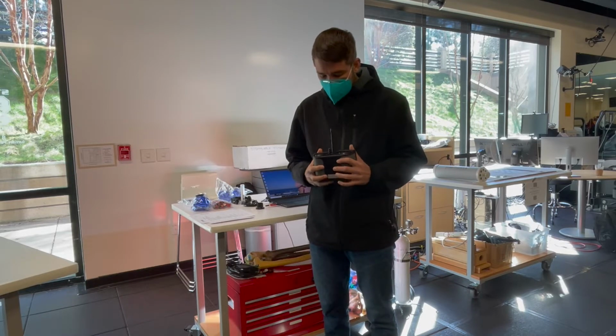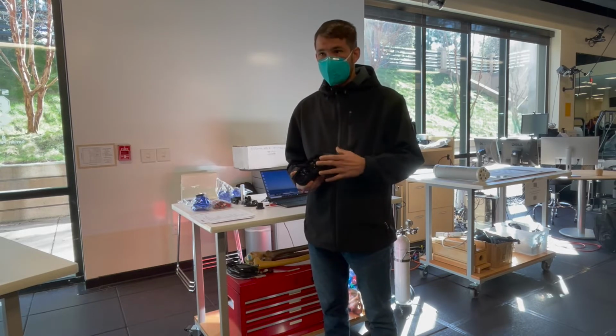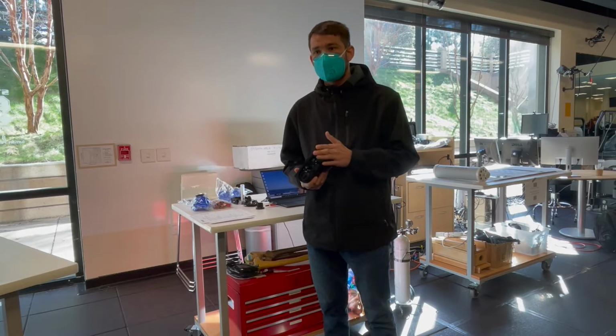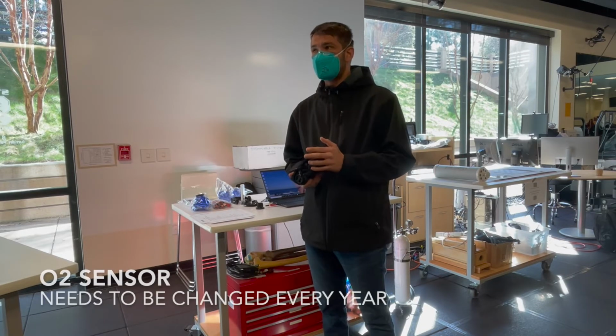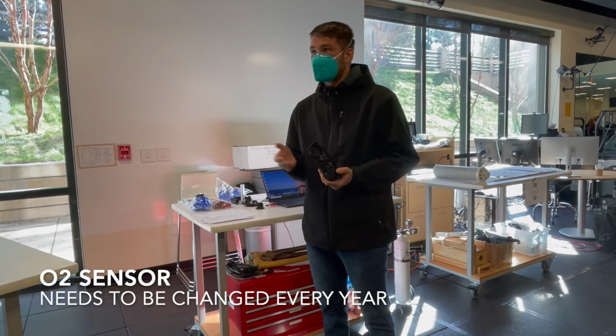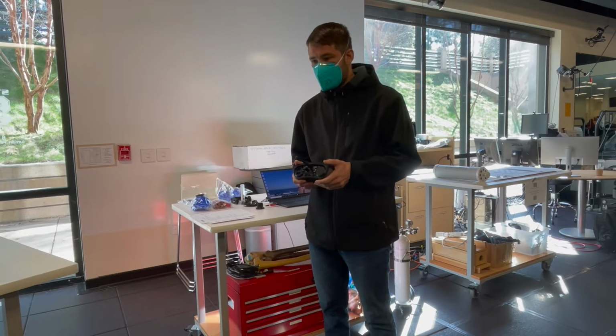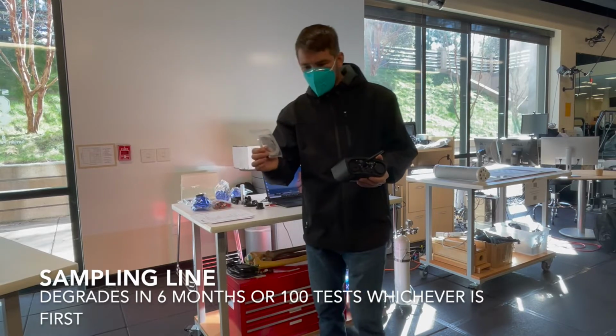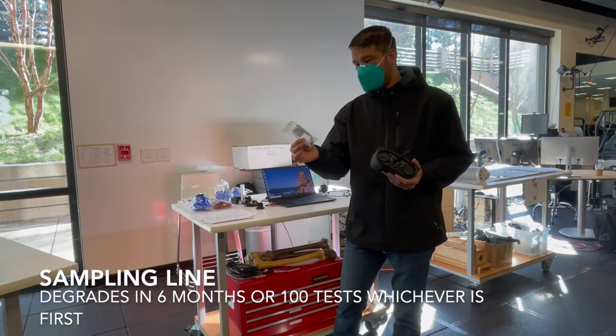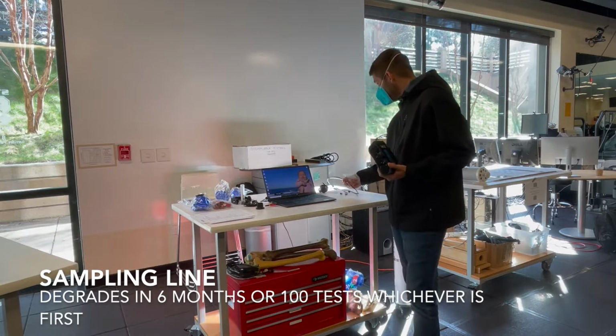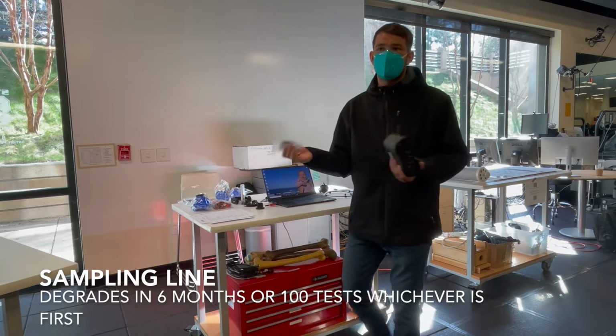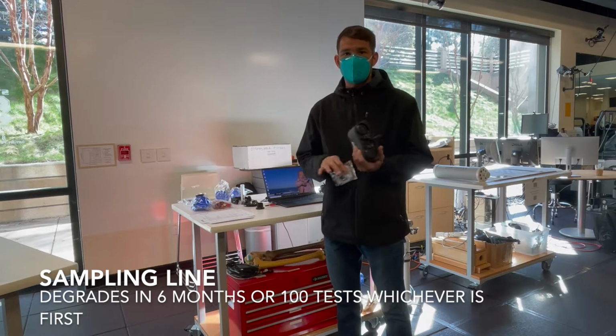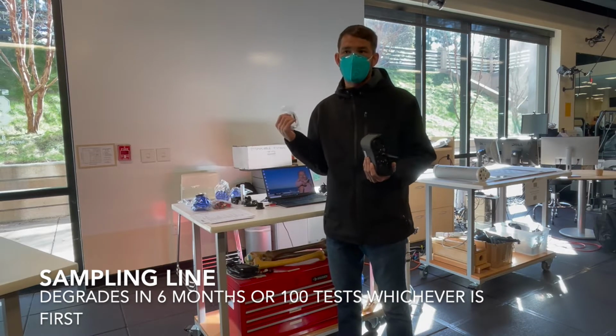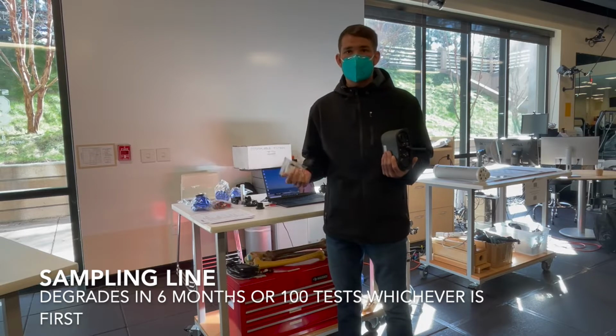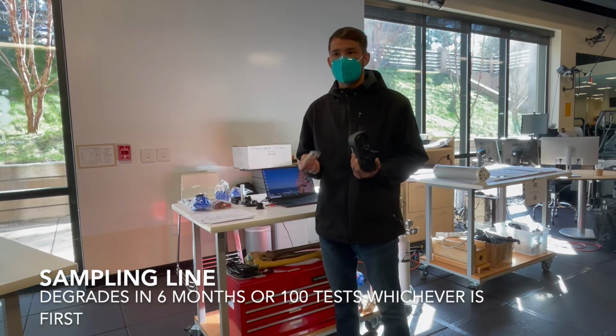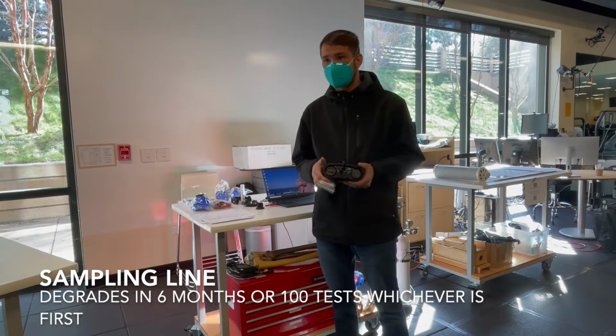And then it has the O2 sensor that can be removed. So this guy, the O2 sensor, will need to be changed every year. That was something we spoke about. It's just part of the year. The sampling line is super important. Basically today with this one, we opened it and pulled it out of the plastic. Essentially the biological timer started. So we could run 0 tests and in 6 months the line will be bad. Or if we run 100 tests in a month, the line is also going to be bad. So whichever comes first, 6 months or 100 tests.